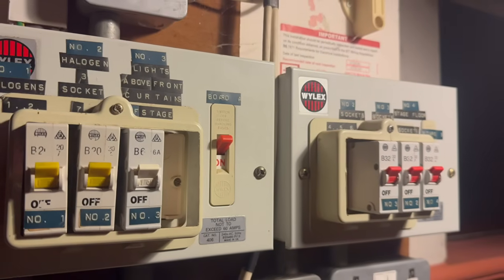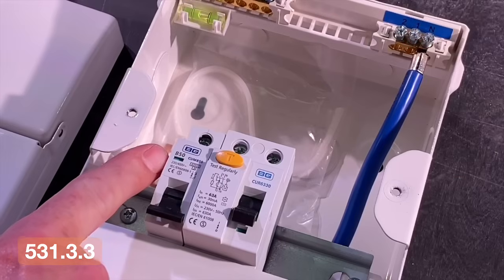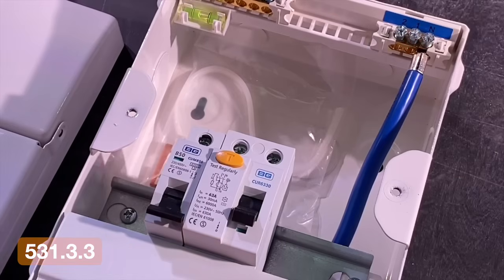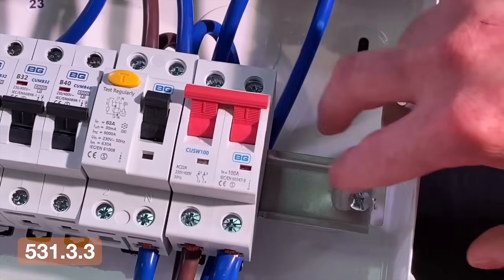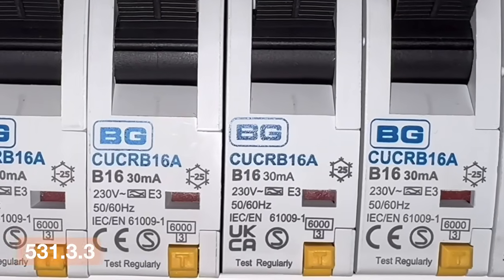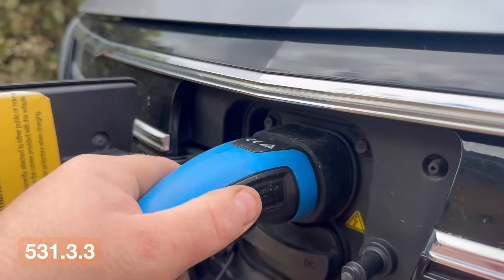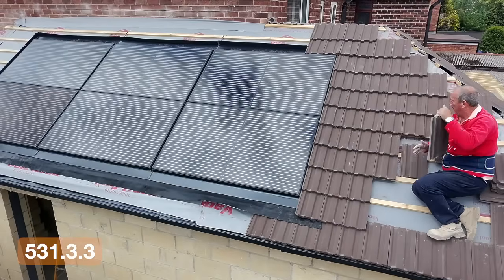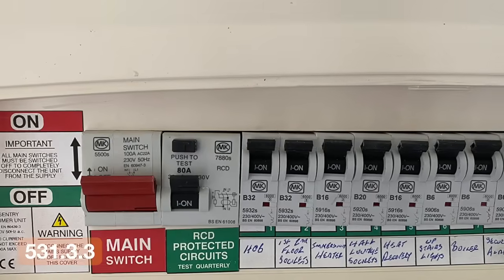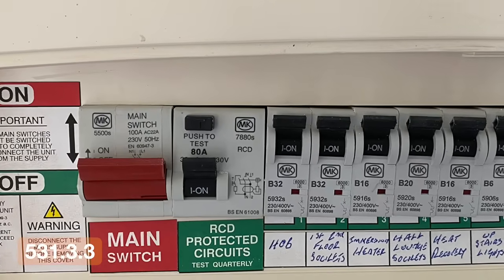RCDs have not been replaced with something completely new, but the way you select them has changed. And this is where older habits can start to cause problems. Regulation 531.3.3 now makes it clear that the type of RCD must be appropriate for the characteristics of the load. That includes DC components and non-sinusoidal currents, which are now common in modern installations. So this is no longer a case of just fitting what has always been used.